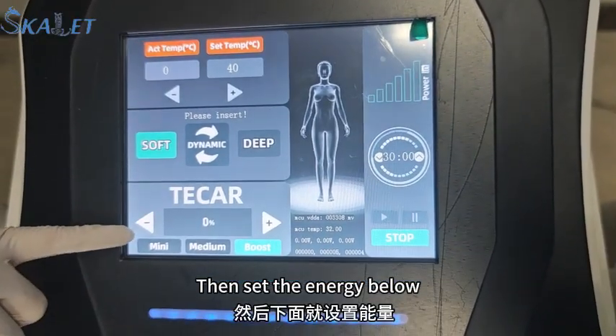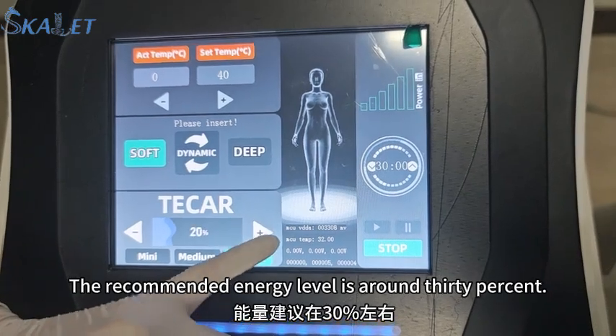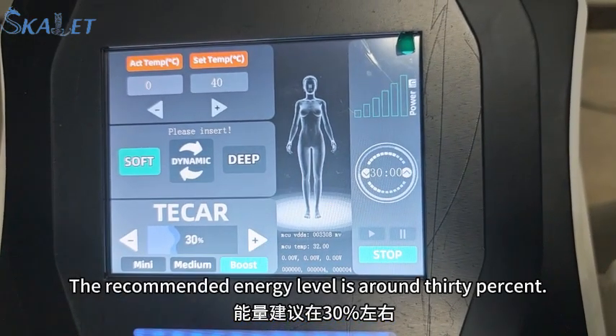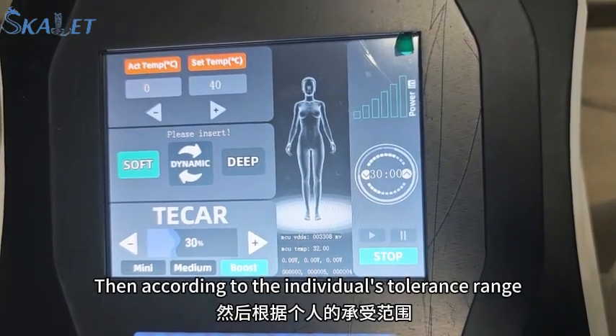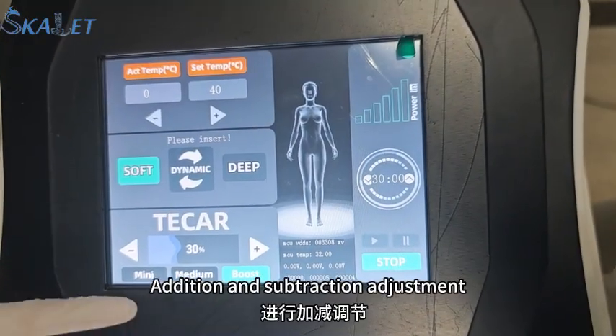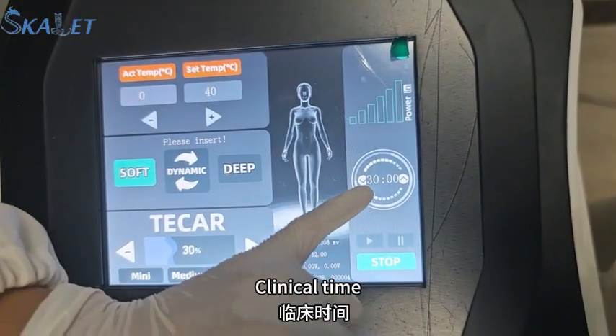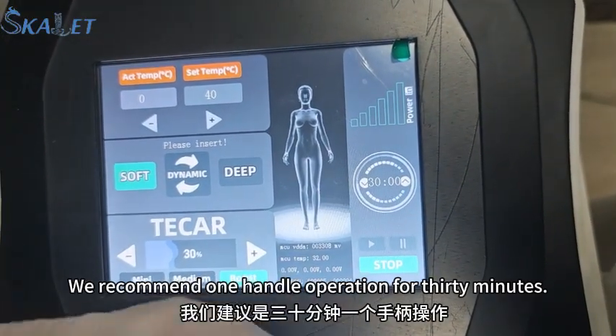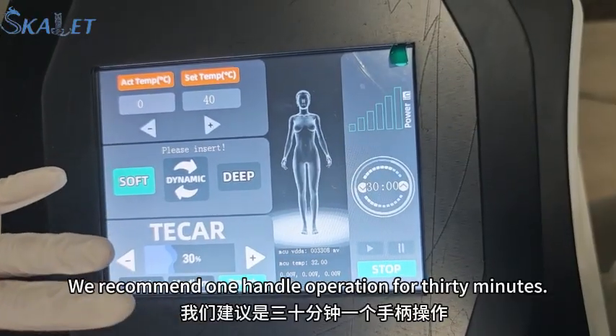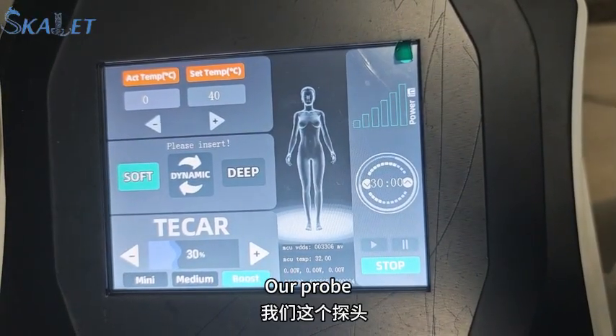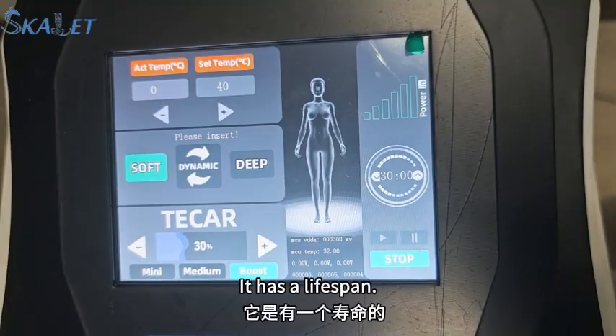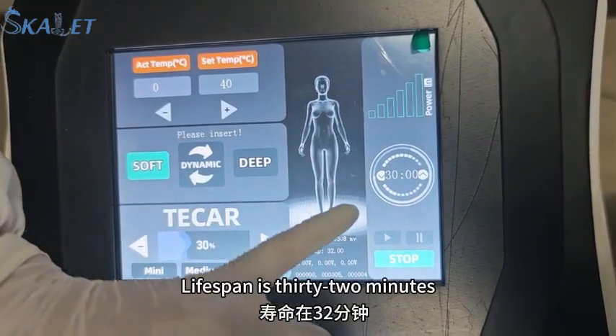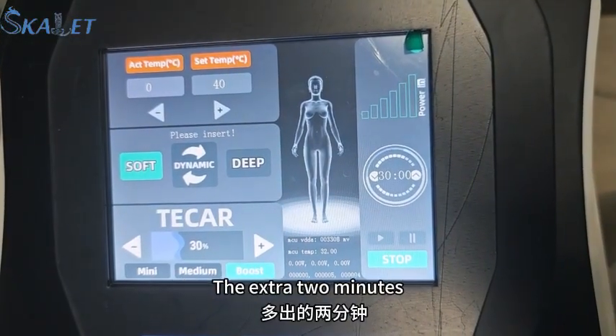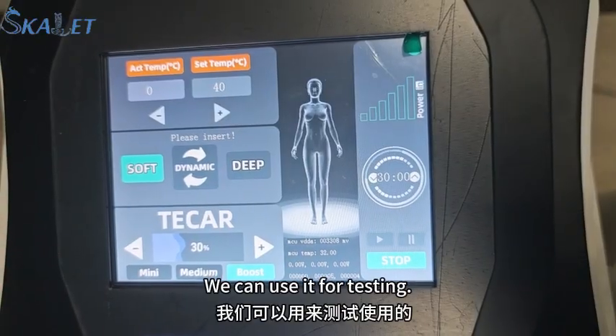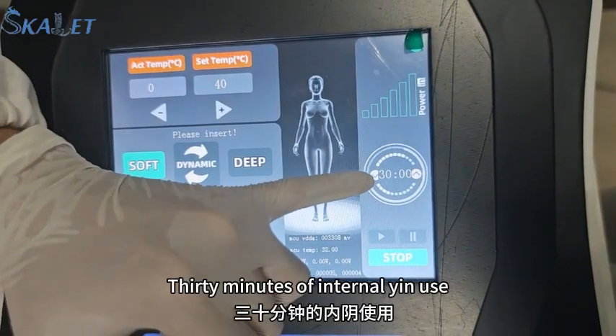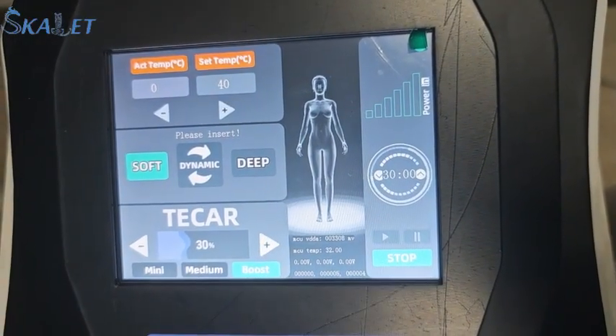Then set the energy below. The recommended energy level is around 30%. Then according to the individual's tolerance range, addition and subtraction adjustment. Clinical time. We recommend one handle operation for 30 minutes. Our probe. It has a lifespan. Lifespan is 32 minutes. The extra 2 minutes, we can use it for testing. 30 minutes of internal in use.